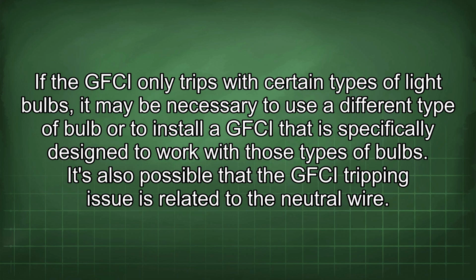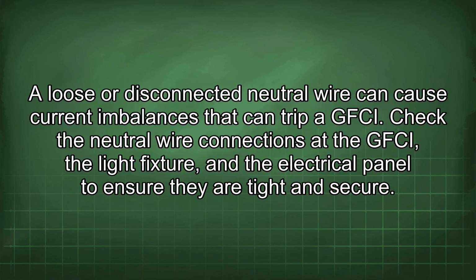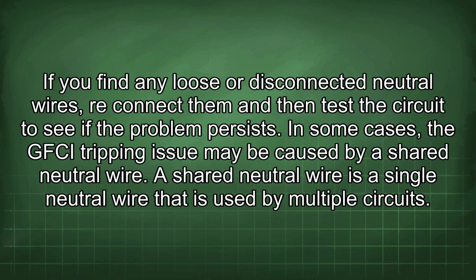It's also possible that the GFCI tripping issue is related to the neutral wire. A loose or disconnected neutral wire can cause current imbalances that can trip a GFCI. Check the neutral wire connections at the GFCI, the light fixture, and the electrical panel to ensure they are tight and secure. If you find any loose or disconnected neutral wires, reconnect them and then test the circuit to see if the problem persists.